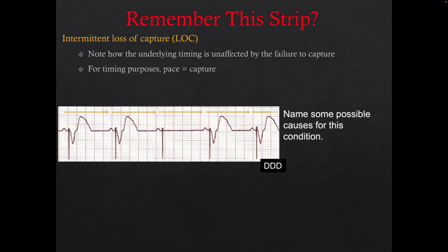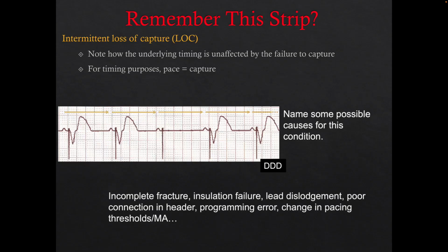So with these devices though, right, they're coded. There could be insulation breaks. There could be issues with this. There also could be what happens if the patient had a massive MI, right? There could be damage to tissue, and sometimes certain medications can also cause what we call pacing threshold increases, like amiodarone. The way it affects the tissue of the heart, it can sometimes increase pacing thresholds. So sometimes we need to give them a better output. And that's typically more so long-term with the implantable devices.